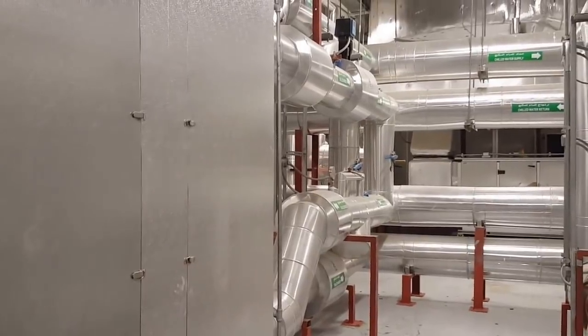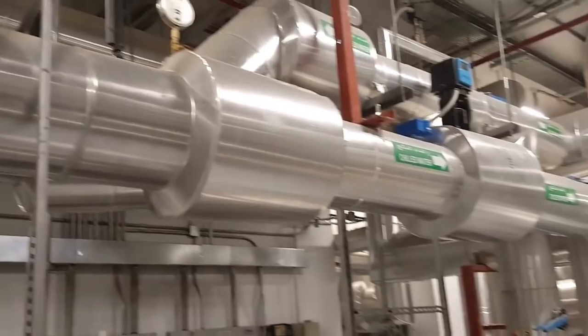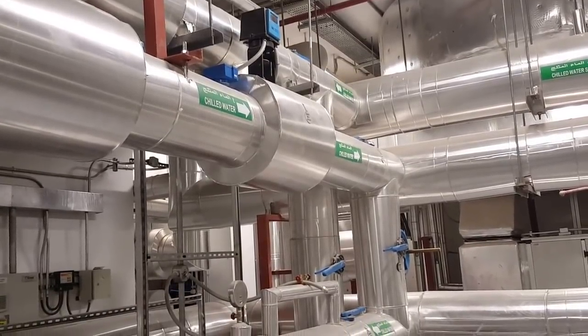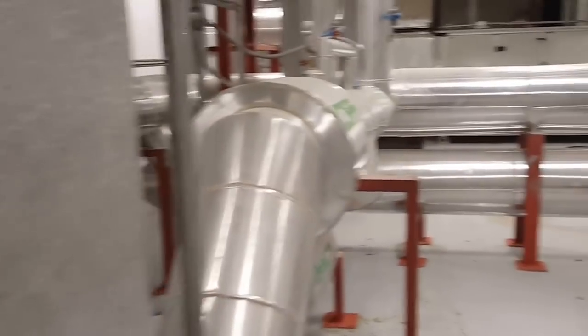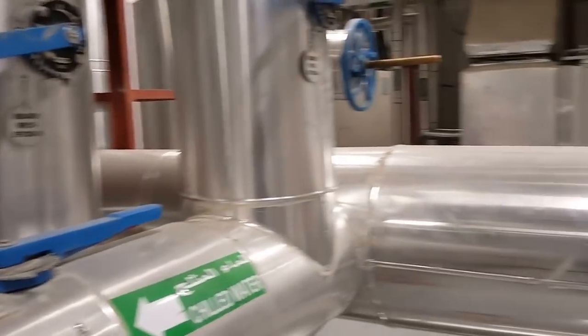I already showed the downside of the pipe; this is the upside. You can see here the same position — this is a heat exchanger with a PRV installed with the pressure gauge. The chilled water supply is coming here; one line is going to the building side and one is returning to the district cooling plant. We installed three heat exchangers: two are working and one is a standby.